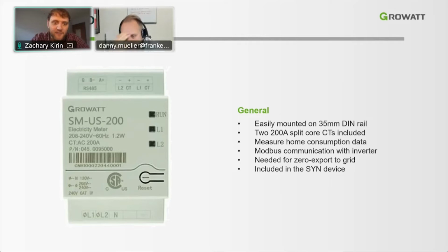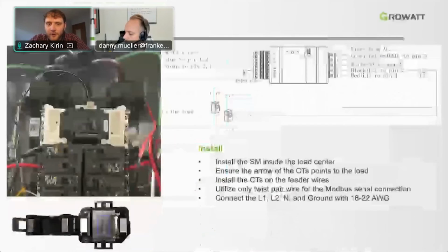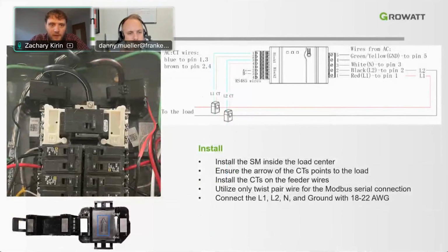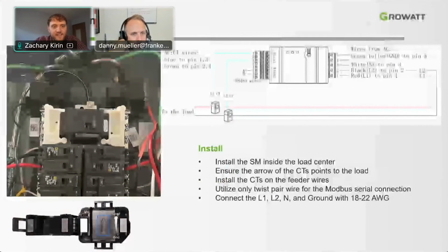But the SYN device has the smart meter built in. So if you were to procure the SYN device at a later time, you'll no longer need the smart meter, or if you have the SYN device, you wouldn't need the smart meter anyway. So this is strictly for those inverters that are on grid only. There's no backup functionality.